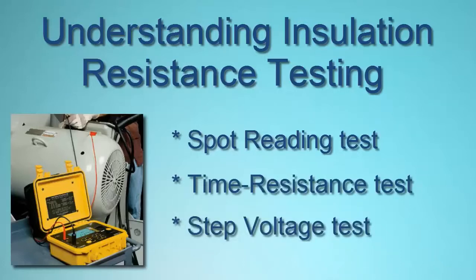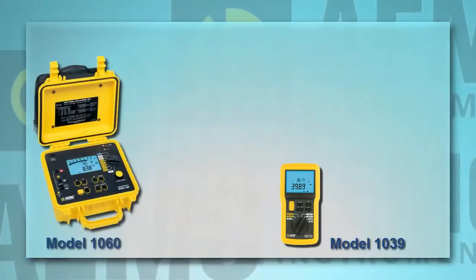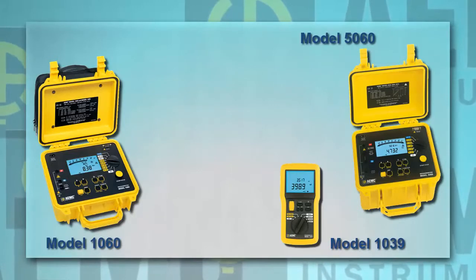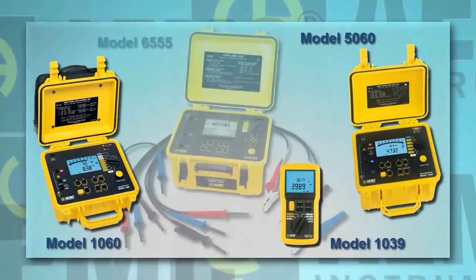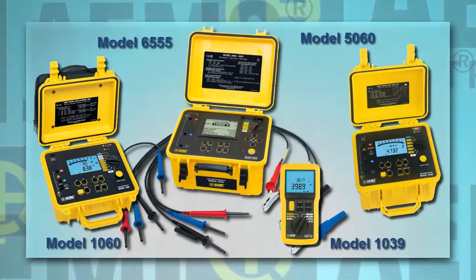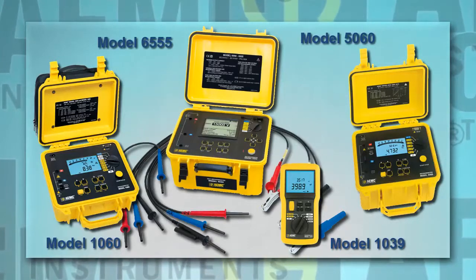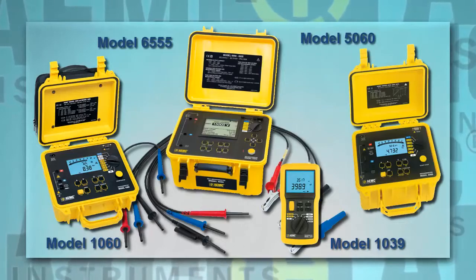These three tests are used primarily to test motor, generator, cable, and transformer insulation. To perform these tests, you will need a megohmmeter with a timed test function. AEMC Instruments offers a complete line of megohmmeters designed for insulation testing, ranging from 100-volt handheld instruments to heavy-duty models providing test voltages up to 15,000 volts. With some models, you can download and analyze the results on a computer running AEMC's DataView software.